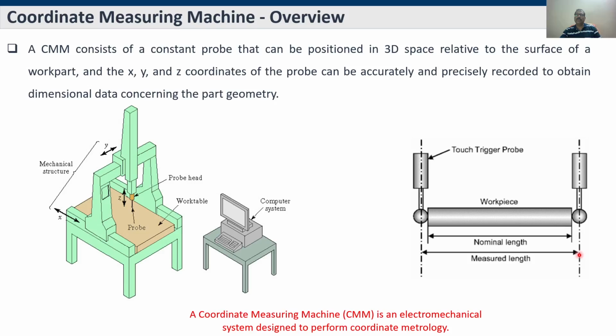Then you will be able to know two different coordinate positions. Here you will have X1, Y1, Z1, or here you will have X2, Y2, Z2. With that difference, you can understand the workpiece length. So the distance between this center axis of the probing system and the other one will be called the measured length. What you have measured will be shown as the measured length. But the nominal length or workpiece length is different. Why? Because the diameter is involved here. Radius, actually, two times the radius. So the diameter of this probe is involved. Once you obtain the measured length, you have to subtract the diameter of the probing system or probe so that you can get the nominal length.